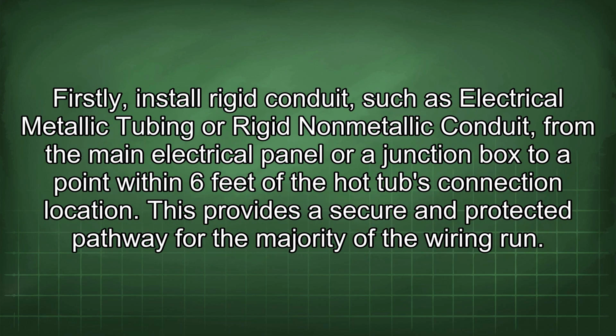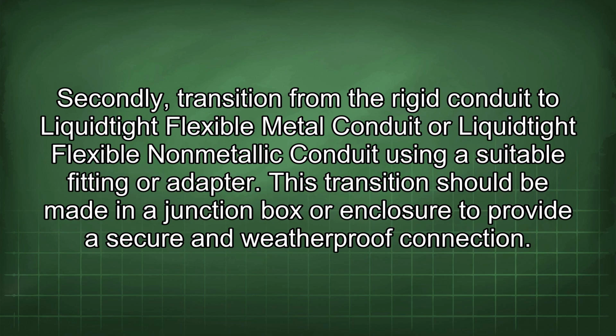Firstly, install rigid conduit, such as electrical metallic tubing or rigid non-metallic conduit, from the main electrical panel or junction box to a point within 6 feet of a hot tub's connection location. This provides a secure and protected pathway for the majority of the wiring run. Secondly, transition from the rigid conduit to Liquidtight Flexible Metal Conduit or Liquidtight Flexible Nonmetallic Conduit using a suitable fitting or adapter. This transition should be made in a junction box or enclosure to provide a secure and weatherproof connection.